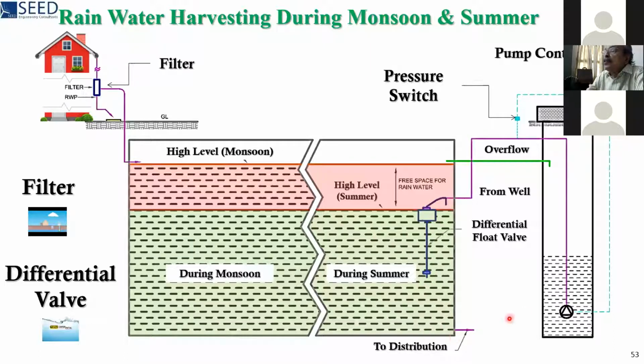And as the water is consumed, the level goes down. The float also moves down up to the stopper. Thereafter, when the water level goes down, along with the float, the lever is pulled and the valve opens. When the valve opens, the pressure in the system falls. It is sensed by the pressure switch, which gives a signal to the control panel, and the pump starts. Water comes in, water fills up. When it reaches this place, the float moving up at this stopper pushes the rod, the valve stops, and the pump is running. The pressure buildup is sensed by the pressure switch, which signals the control panel, and the pump stops.